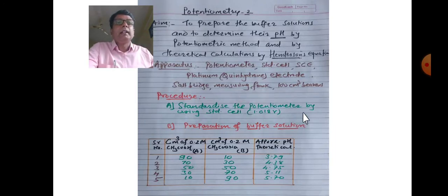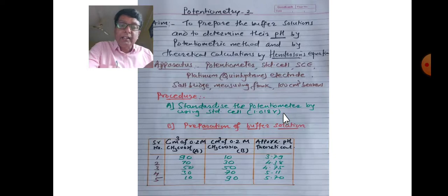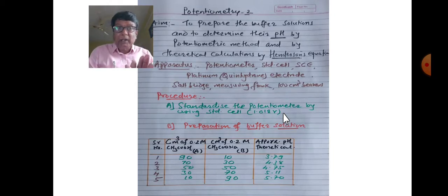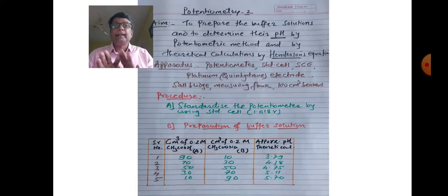Procedure: standardize the potentiometer by using standard cell 1.018 volts. The potentiometer must be standardized first, then take readings. For standardization, the standard cell voltage is 1.018 volts, and the potentiometer reading should show 1.018 to verify standardization is complete.